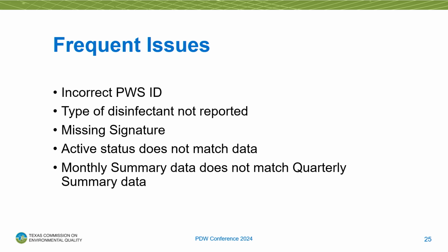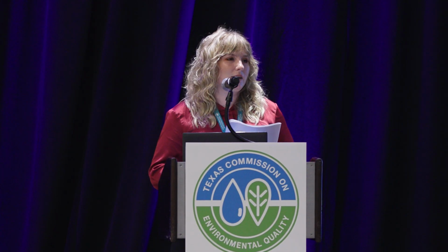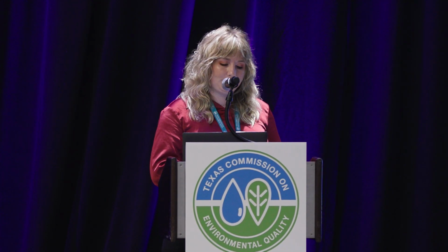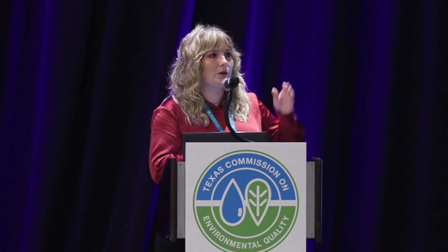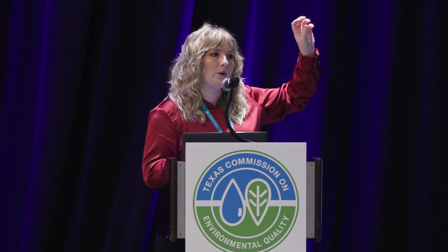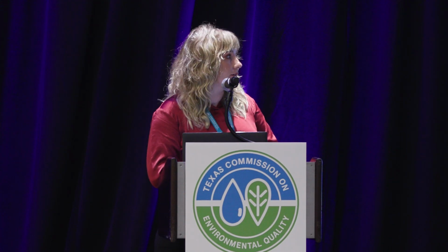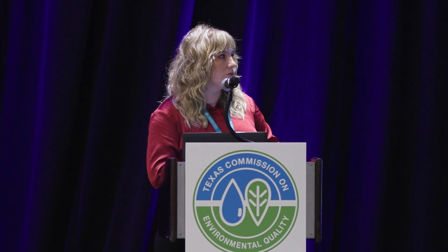For active status does not match the data, that's that PWS activity that I pointed out. Just make sure you're checking yes or no whether your system was active that month or not. Monthly summary does not match the quarterly summary data. That's like if the lowest residual was 0.2, but over here one of your averages was 0.15. Well, we know that's not correct, so that data needs to be rechecked.